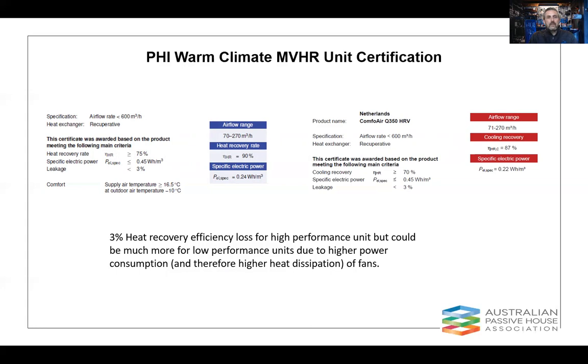efficiency difference. Now, that is really just due to the fact that it's operating under some now warm outdoor air conditions. And what's happening is that heat dissipation that in the cool climate was contributing to efficiency is now actually reducing efficiency. And so you can see from our total energy balance in PHPP, the effect is not insignificant. So we really should start to compensate for that. So there will be a future release of PHPP. I don't know exactly when that is, but it will start now ask you for warm climate data as well. My understanding is there'll be perhaps dual pages, a winter and a summer page, or some calculation for efficiency in both winter and summer conditions, rather than assuming evenness across the whole spectrum.